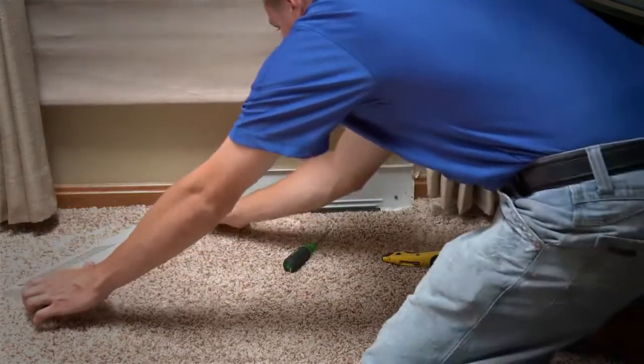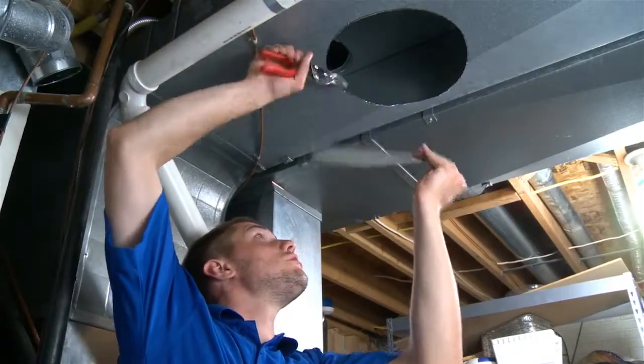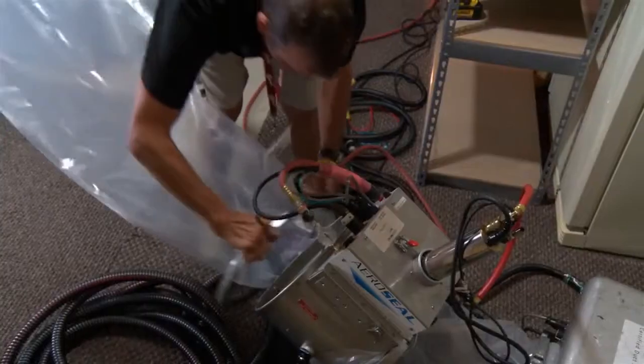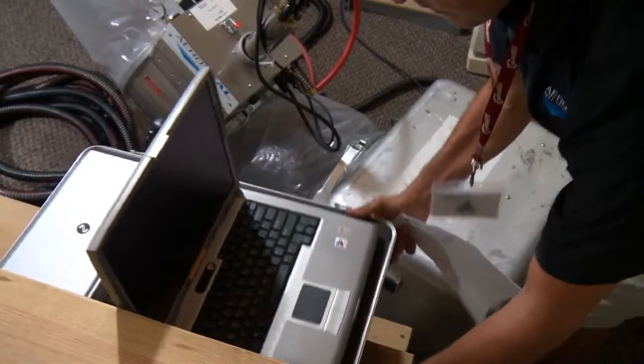First, a technician will install foam plugs into all air duct openings. An access hole is cut into the supply or return plenum, and a temporary collar is attached. The Aeroseal injection machine is then connected to the duct system using a long, flexible plastic tube. A patented computer-controlled injection machine heats up adhesive particles suspended in a liquid.